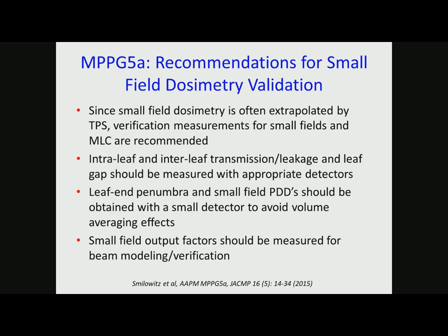Small field dosimetry is a little bit more complicated, so there's a special section in MPPG 5 talking about small fields, MLC commissioning. This is where people get into trouble. If you don't commission the leaf gap or the leakage or intra-leaf leakage and things like that with the appropriate detectors, you can get into trouble.